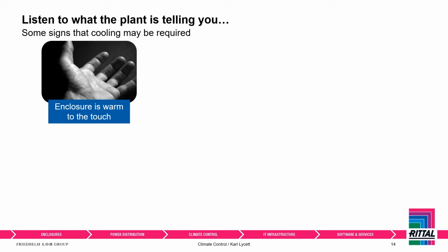On the flip side, if somebody's turned the cooling unit down to 20 degrees, thinking it's a human that needs cooling, which again is a no-no because you're wasting energy, the enclosure sometimes can be cold, which again tells you the opposite. Oh, hang on, maybe I'm cooling too much here and I'm wasting energy and I'm burning pound notes. So you need to think about it in both manners.